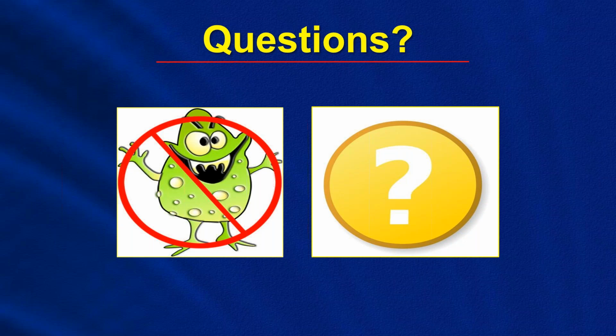Our first question is, should we be ATP testing instruments that have been sterilized or endoscopes that went through high-level disinfection? Should we be testing instruments that have been sterilized? You can test instruments that have been sterilized or scopes that have gone through high-level disinfection. But these items have already gone through their own process of indication. For steam instruments, you have steam indicators, high-level disinfection parameters. Those parameters should have been met already. So I'm just not sure what the purpose of testing sterile or HLD items is.